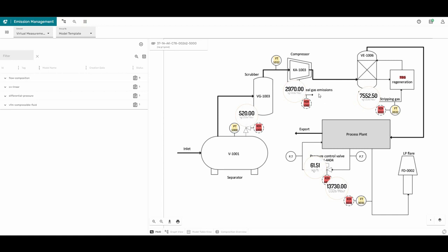Another one is seal gas emission from compressors, known but hard to capture precisely on a lot of facilities. You could combine the sensors, data sheets and metrics you have in place around your compressor to say something about the most likely methane and other types of hydrocarbon emission out from the seal, and transfer that back to, for example, CO2 equivalents, if that's what you mainly are measuring or reporting on.